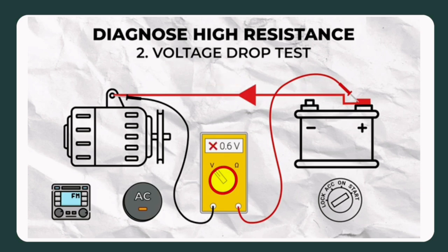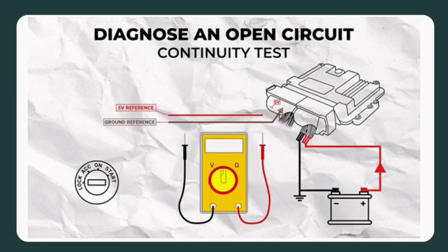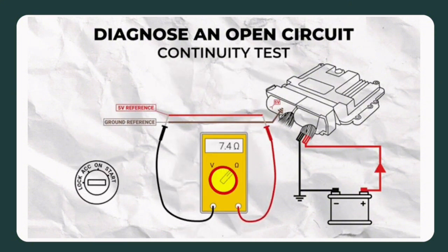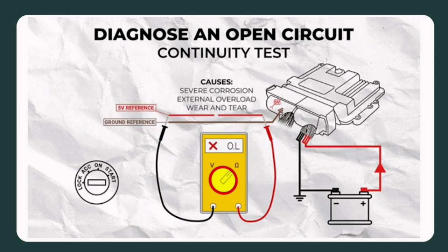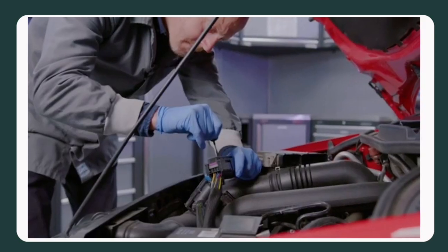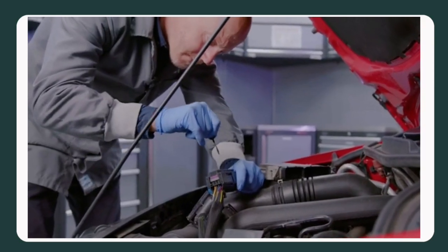An open circuit can be diagnosed again by checking continuity of the wiring, but instead of getting a high resistance reading, you will see OL or open circuit on the multimeter. These faults are caused by a complete break in the wiring caused by severe corrosion, damage from an external overload, or from general wear and tear over time. The other causes of an open circuit could be due to poor terminal tension.